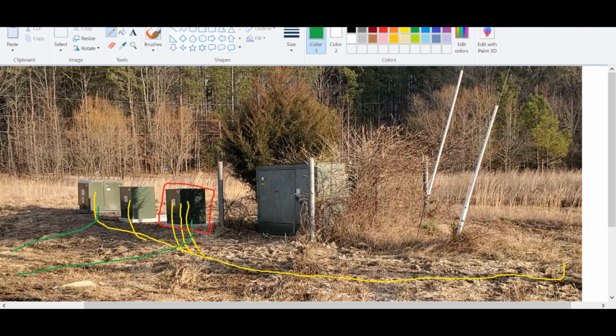From that point, I guess I could keep the single phase service attached to the building if I wanted to, but more than likely what I'll do is I'll have them remove this guy here also, and that one will be gone. And then I'll buy a dry transformer to convert the 480 to 240 single phase and just put that in the building for my smaller loads, like outlets and power tools. That way I only have one bill coming to the building from the new 3-phase transformer.